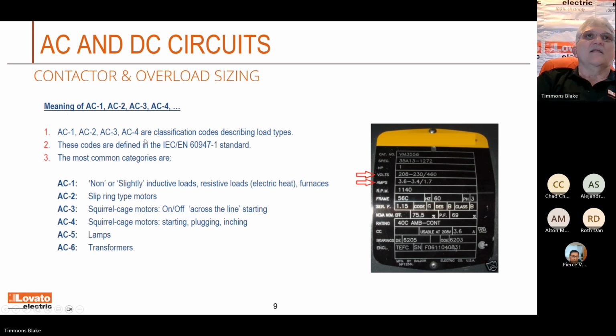All right. Now, when we talk about motors, I wasn't sure what motor brand y'all handled. I didn't want to offend anybody, so block that out a little bit. But when you look at motors, people always ask, I said, well, what's the amperage you're looking at? Always go to the running amps or the full load amps. When we size things, we go by amps. I'm not always concerned what the voltage is, but I do want to know what amps. A lot of times I'll ask them, well, what's the voltage of the motor?